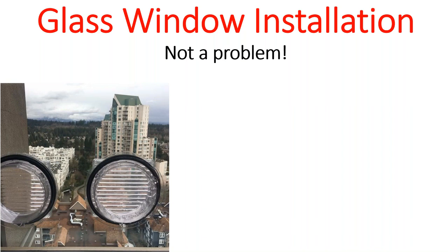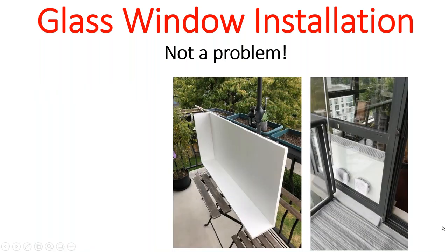Now, what if you have a glass building? That's not a problem. This is an actual job that was installed somewhere, I think, around Toronto, where they sourced an 8-inch grill that is kind of clear plastic with the same free area as the grill supplied by the factory. And then they created a composite material, white material, to mount the unit on. And if you look at the right-hand picture, you see a finished result there. I think this job has 12 of them on there, and everybody's happy because it serves the need without completely destroying the ambience of the building by having something hanging out there.